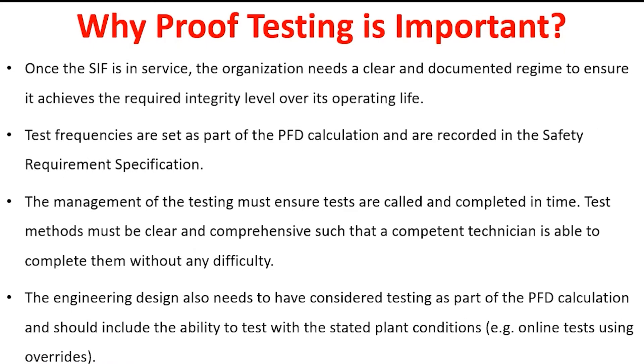Once the safety instrumented function system is in service, the organization needs a clear documented regime to ensure it achieves the required integrity level over its operating life. Once the plants are alive and in working condition, the management should have clear documented records for the proof testing of the instruments. Test frequencies are set as part of the PFD calculations and are recorded in the safety requirement specifications.